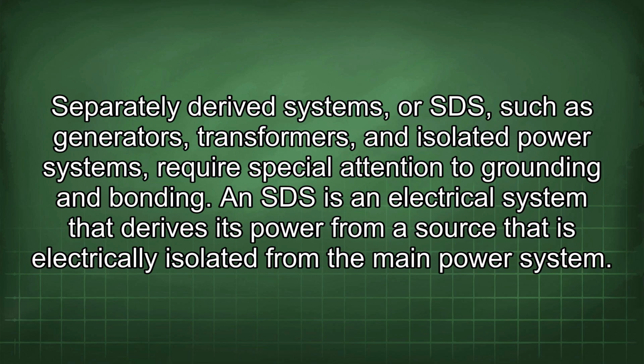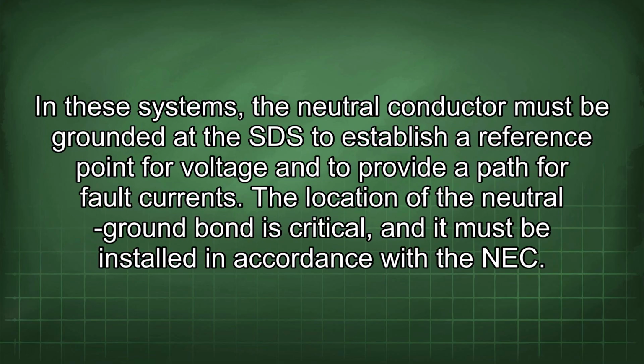Separately derived systems, or SDS, such as generators, transformers, and isolated power systems, require special attention to grounding and bonding. An SDS is an electrical system that derives its power from a source that is electrically isolated from the main power system. In these systems, the neutral conductor must be grounded at the SDS to establish a reference point for voltage and to provide a path for fault current. The location of the neutral ground bond is critical, and it must be installed in accordance with the NEC.